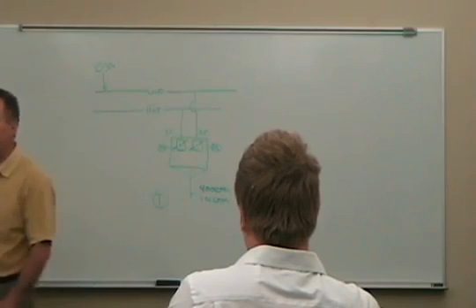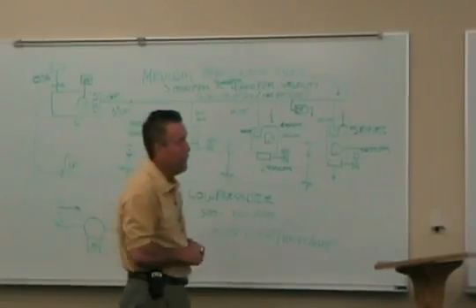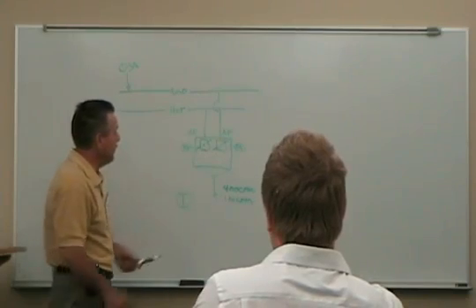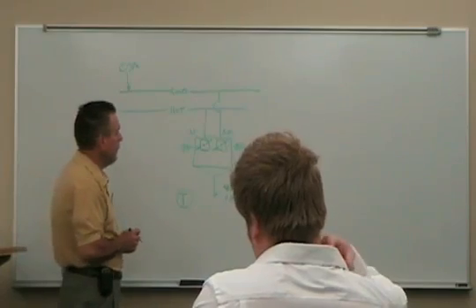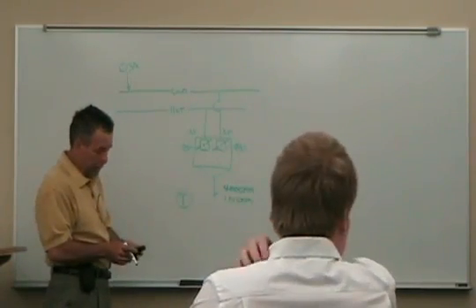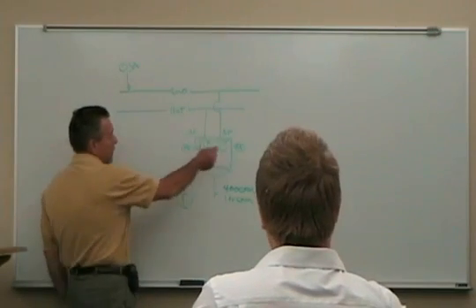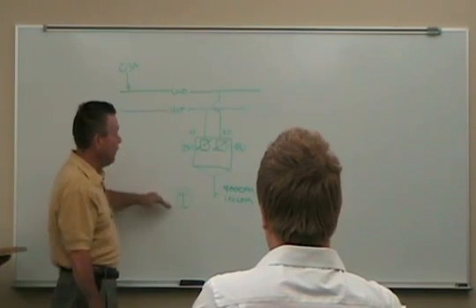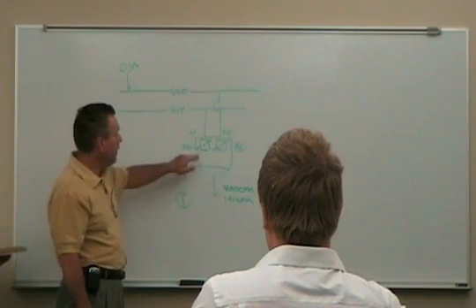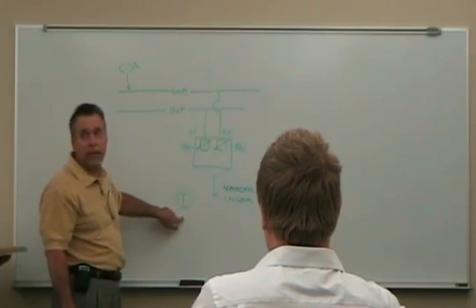That's generally open to how the system was designed, where the outside air is. But you can see that it offers some programming issues on these, how to maintain minimum airflow. In most cases in the old hospitals, these are just constant volume. But they can be retrofitted to variable volume applications. In a constant volume application, this would just open and close, depending on what the thermostat is doing. I'm either calling for heating or I'm calling for cooling, or the space is somewhat satisfied. So these two dampers open and close to maintain temperature in the space.